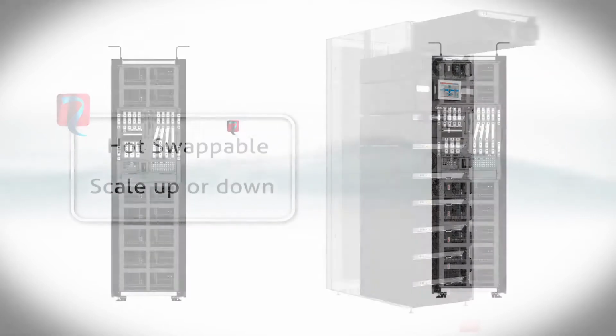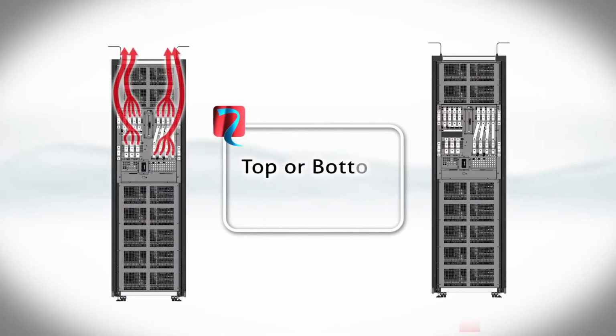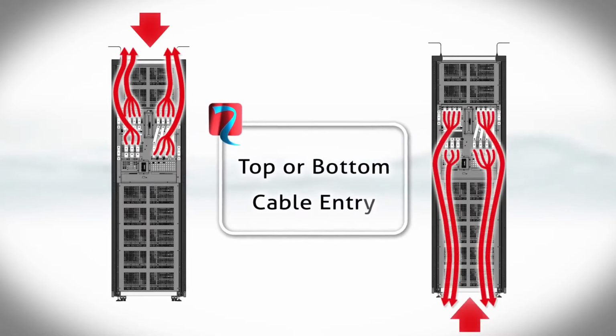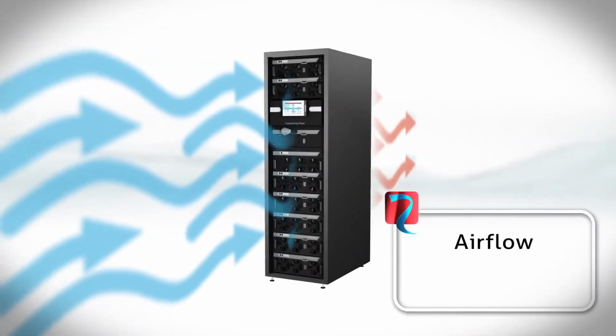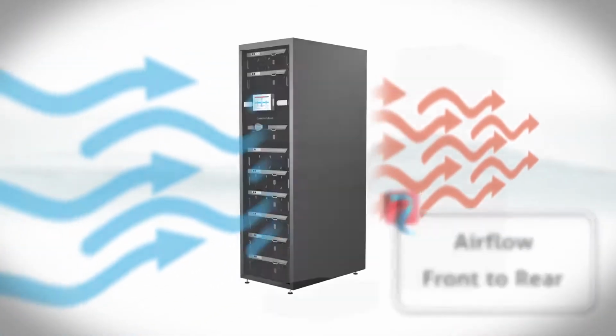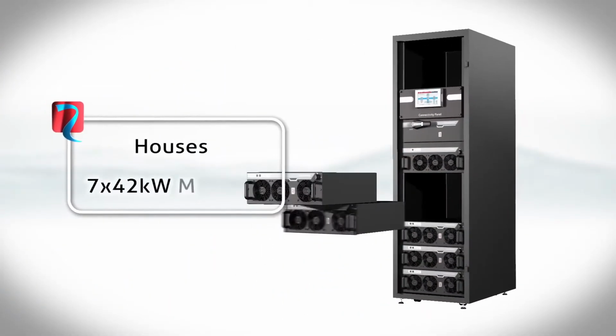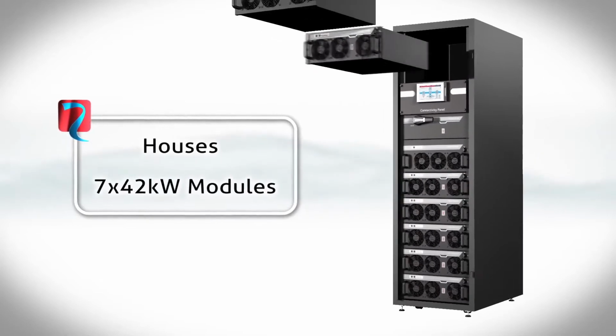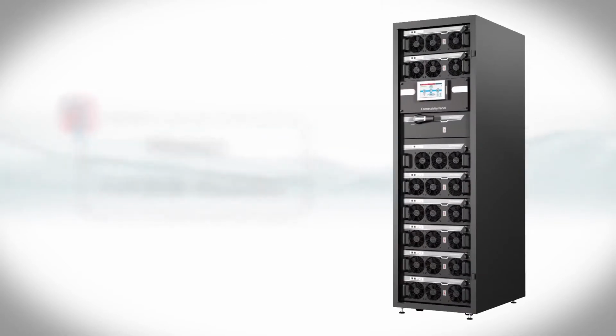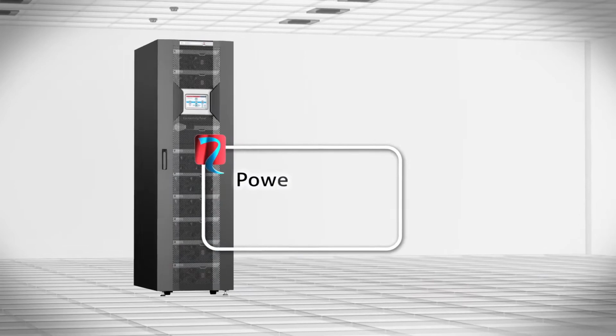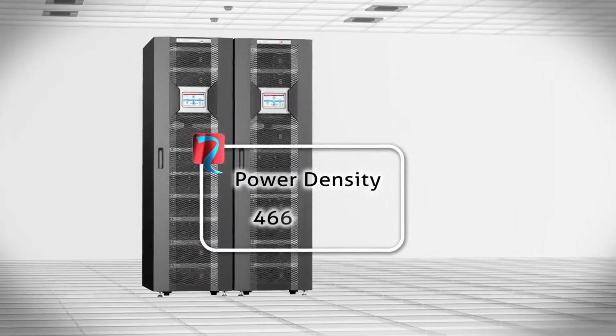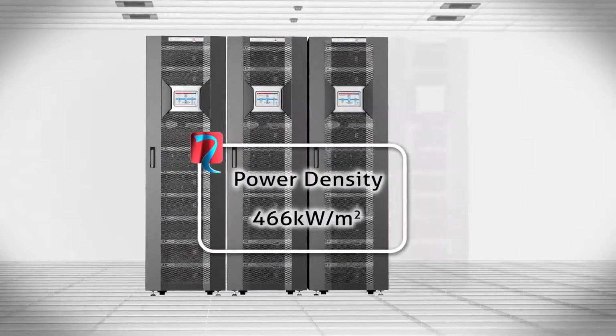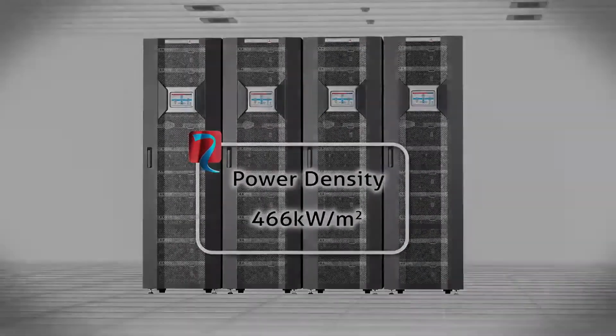Multi-power initial installations are easy and painless, with top or bottom cable entry, plus airflows like server racks, which are front to rear. Data centres grow, so the multi-power needs to grow with it. With the ability to house 7 42 kilowatt modules in one cabinet, and up to 4 cabinets in parallel, delivering over 1 megawatt, giving it one of the highest power densities in the market at an incredible 466 kilowatts per squared metre, including redundancy.